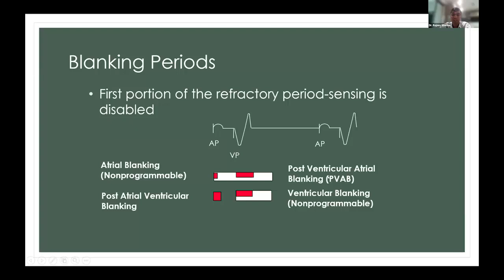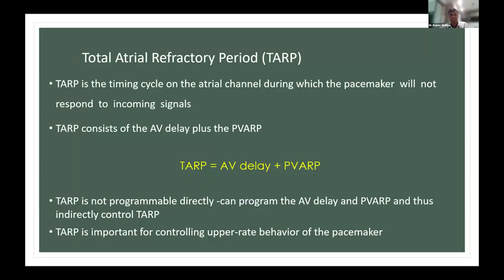It is the timing cycle on the atrial channel during which the pacemaker does not respond to incoming signals. TARP consists of AV delay plus PVARP. It is not directly programmable, but we can decrease or increase the AV delay or PVARP and then program the TARP. This is important for controlling upper rate behavior, especially in young and physically active patients. As we can see here, there is a sensed event, then AV delay, and then PVARP. So the sum of this is TARP.